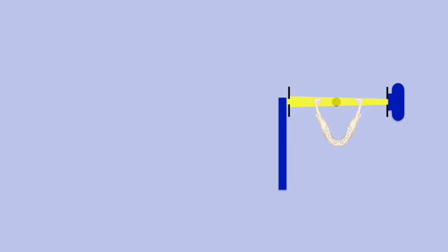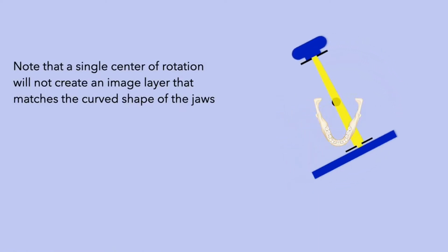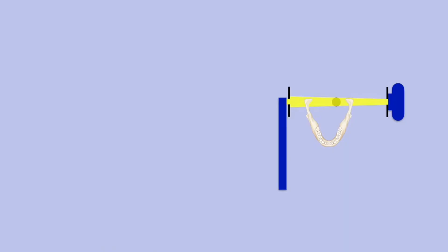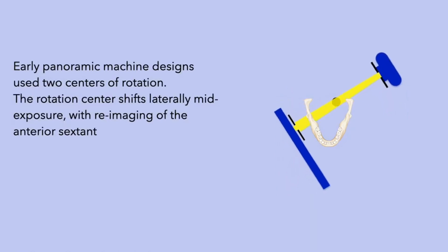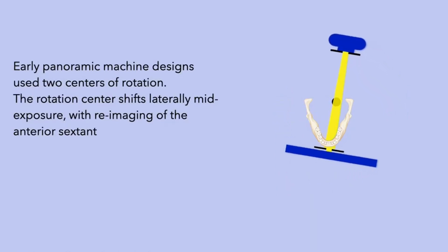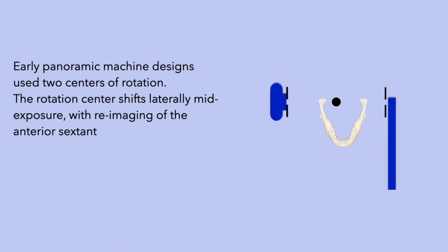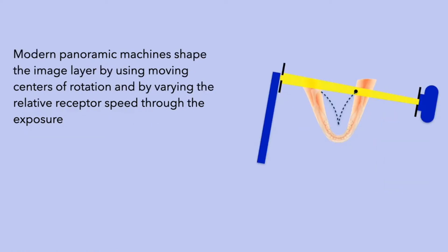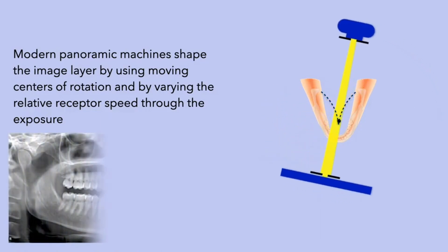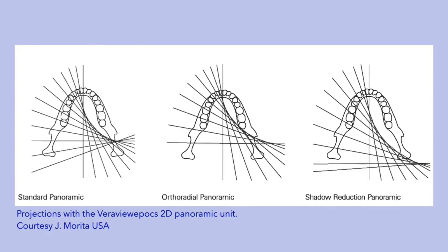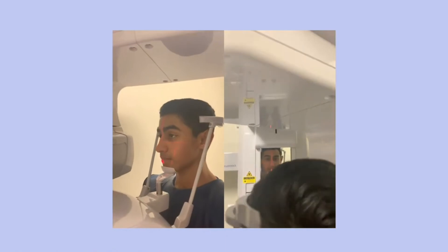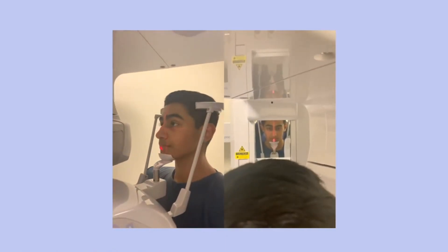Next, let's apply these principles to imaging the jaws. Note that a single center of rotation does not create an image layer that matches the curved shape of the jaws. Early designs of panoramic machines used two centers of rotation. The first imaging arc encompassed the condyle through the canine of the contralateral side, and the rotation center would then shift laterally with re-imaging of the anterior sextant and the contralateral jaw. Modern panoramic machines shape the image layer using moving centers of rotation and by varying the relative receptor speed through the exposure cycle. Many manufacturers offer options for different image layers to accommodate jaws of varying shapes and sizes. To facilitate patient positioning into the image layer, panoramic machines are equipped with laser lights that guide patient positioning.